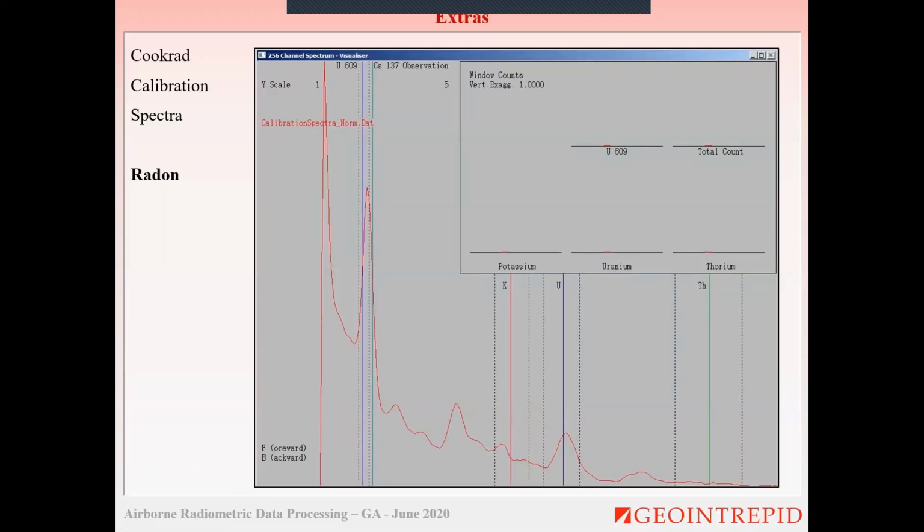And I remember once I had to energy calibrate one of those spectra because I didn't like it. You just duplicate the one spectrum, because the calibration spectrum is only one spectrum, so you duplicate it by 1,000 times and let that energy calibration tool run over it, and then you're sure that the calibration spectrum is also energy calibrated. That is nowhere specified in the technical specifications, and it's difficult to get the contractors to give you the calibration spectra. They duck and dive and moan.